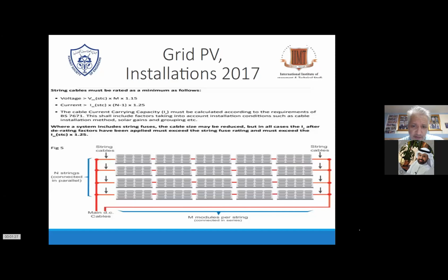Here, like I said, if you go into a maintenance or installation, you have these string fuses. So you have to check the cabling and the string fuses. Normally it's a factor of 1.25. In some hotter regions, it's even 1.5. Of course, the higher you go, the more problems you encounter, because normally it's a factor of 1. So if you have a 10 amp current rating of a module, and you use, for example, 12 amps, that's fine. If you use 15 amps, it's already a little bit high, and the possibility that it breaks down at a normal current is minimal.